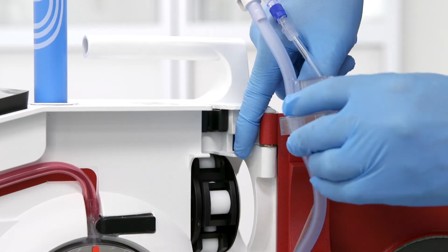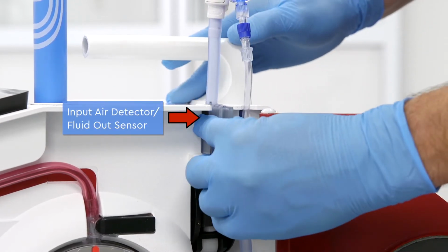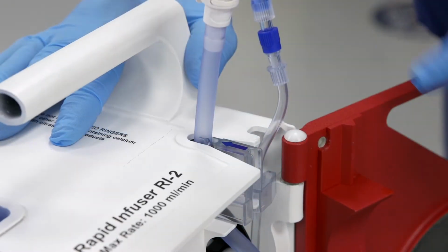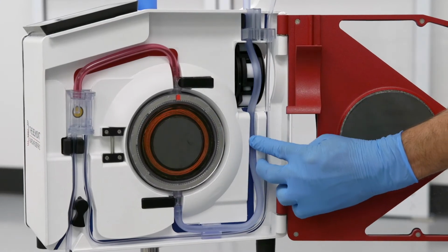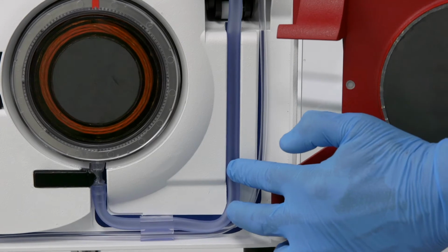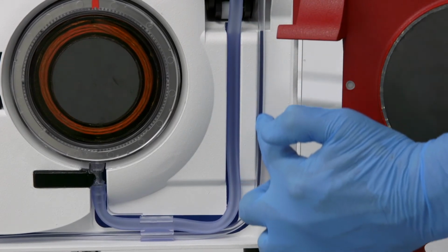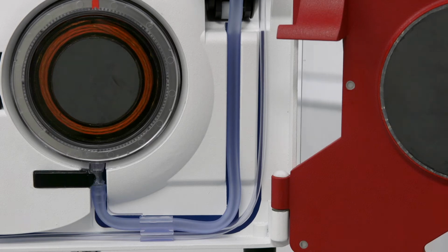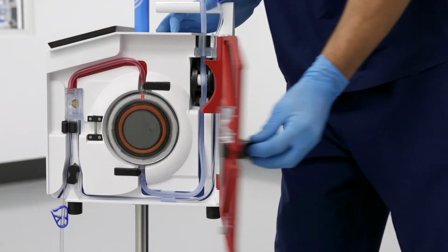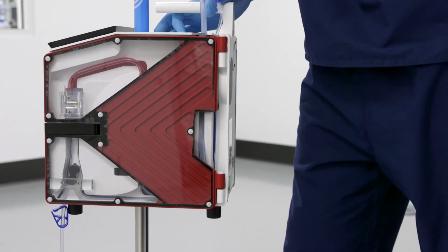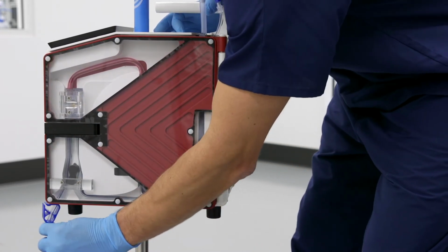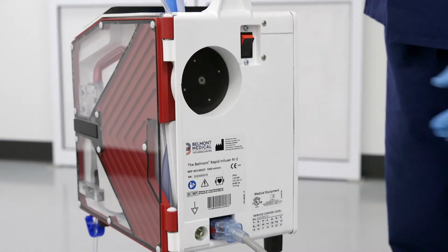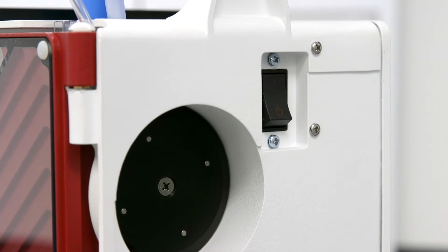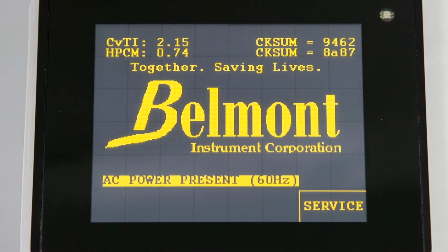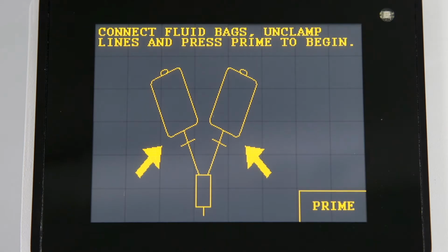Next, fit the interlock block on top of the shelf. The blue arrow should be upright, pointing towards the ultrasonic air detector. The interlock block will be flush with the top of the machine. Thread the wider tubing over the center of the roller heads. Make sure that the larger tubing is in the groove of the wider blue line and the smaller tubing is in the groove of the thinner blue line. Avoid stretching, kinking, and cross-threading the tubing. Finally, close and latch the door, making certain the pump tubing is not caught. You are ready to power on the system. Press the power button firmly to the on position, which is located on the back of the device. After a brief self-test, operation instructions will be displayed on the screen.